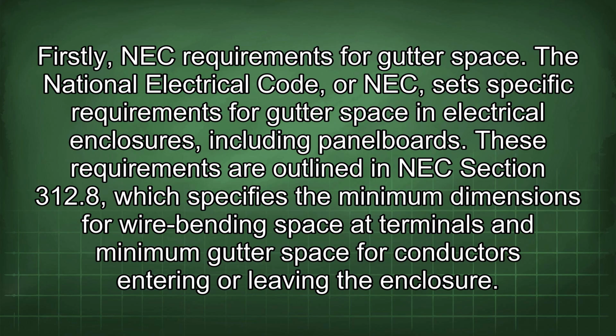Firstly, NEC requirements for gutter space. The National Electrical Code, or NEC, sets specific requirements for gutter space in electrical enclosures, including panel boards. These requirements are outlined in NEC Section 312.8, which specifies the minimum dimensions for wire bending space at terminals and minimum gutter space for conductors entering or leaving the enclosure.